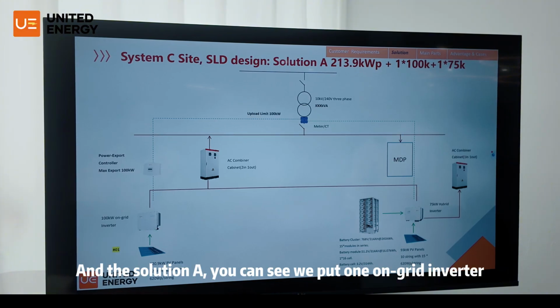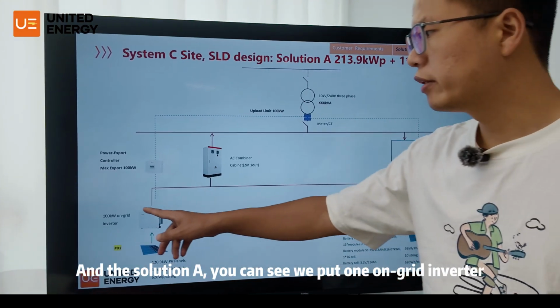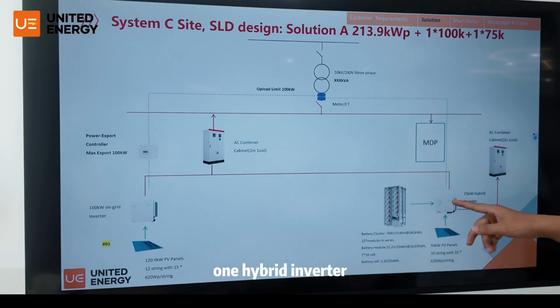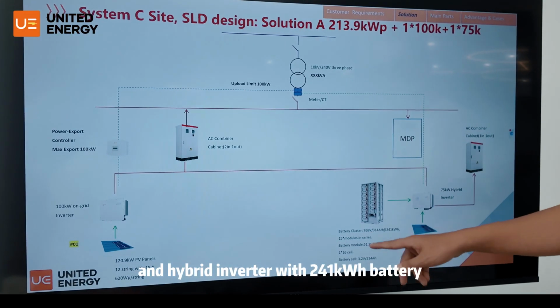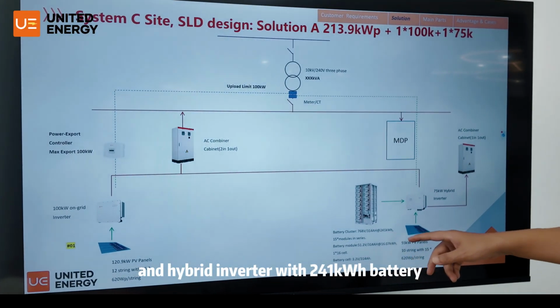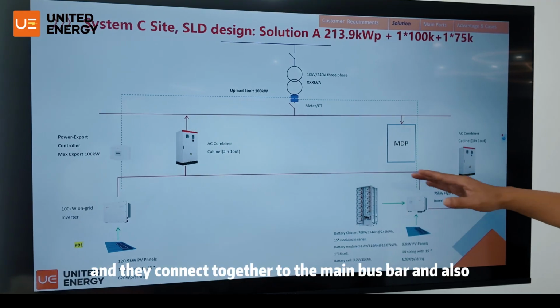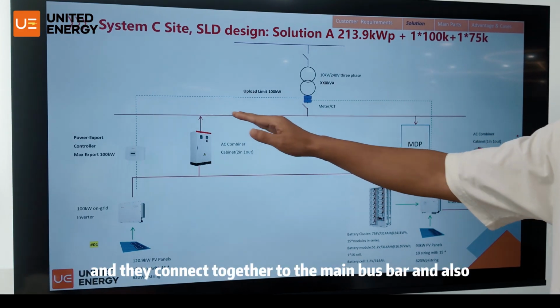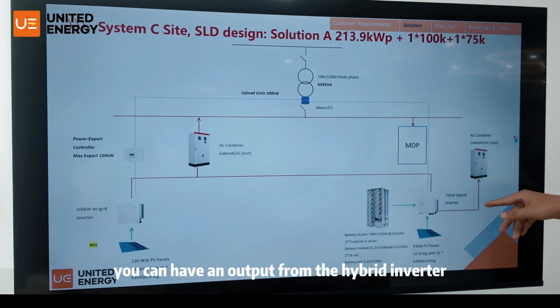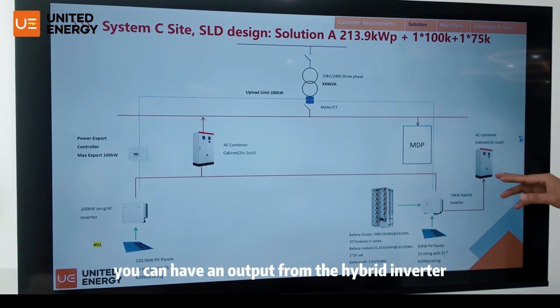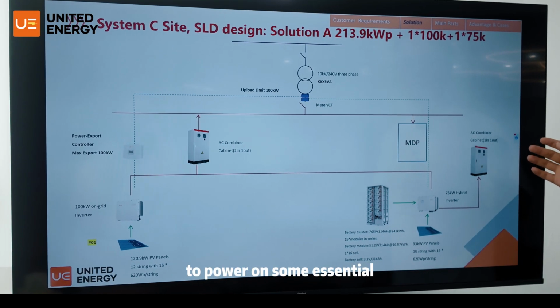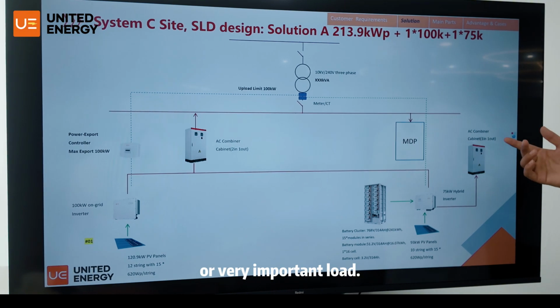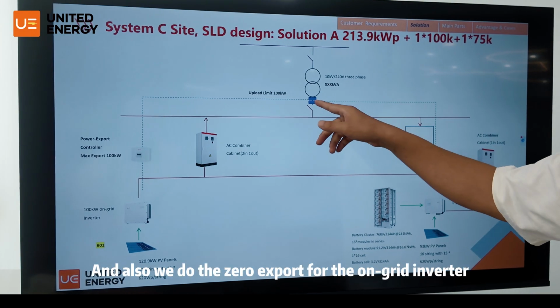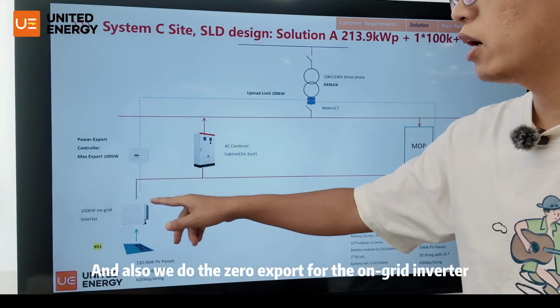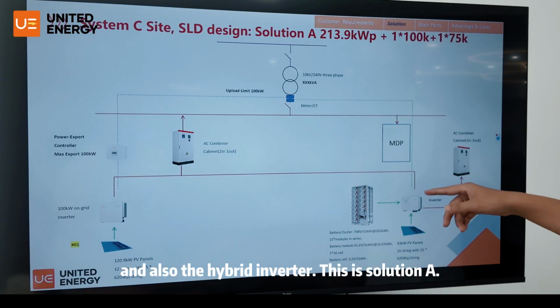For solution A, you can see we put one on-grid inverter and one hybrid inverter with a 241 kilowatt hour battery, and they connect together to the main bus bar. You can also have output from the hybrid inverter to power some essential or very important load. And we do zero export for both the on-grid inverter and the hybrid inverter.